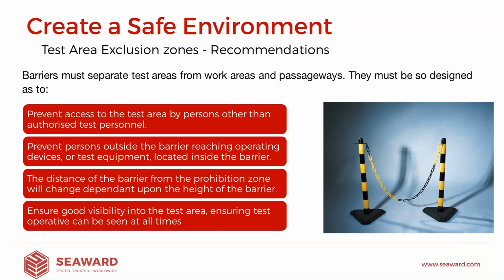So there are set distances in EN 50191 that will help you to determine how big your test area needs to be. Now, one thing to consider is if you are creating a prohibition zone, always make sure that whatever you do choose to use to block off the walkways or work areas from the test area, it retains good visibility into the test area.